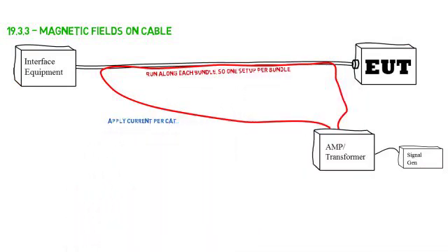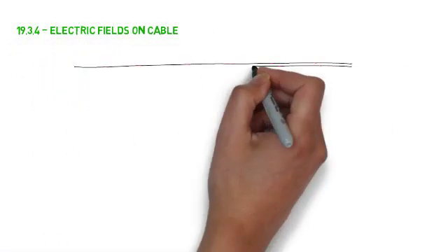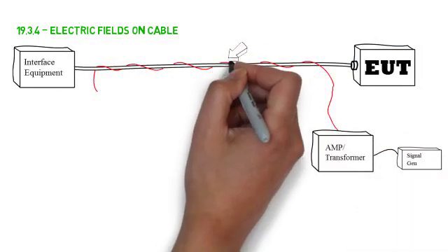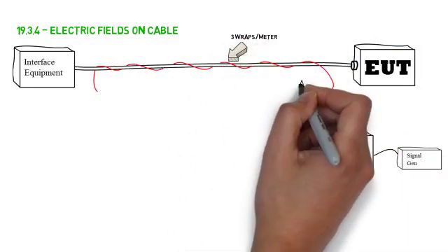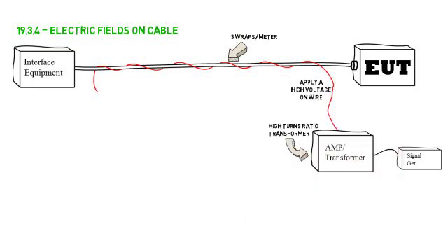For electric fields on the cable, wrap a high voltage wire around the cable a minimum of 3 wraps per meter. Apply a voltage to the wire in accordance with the category. This high voltage is usually achieved with an audio amplifier and a high ratio transformer.